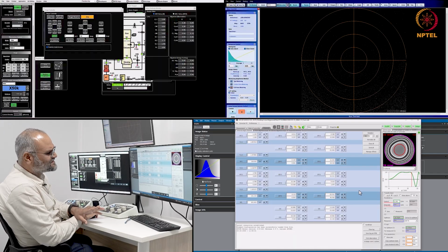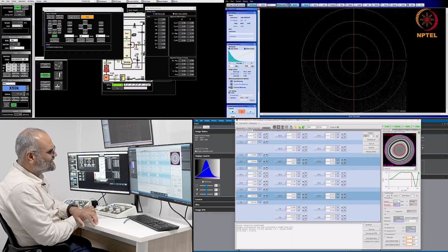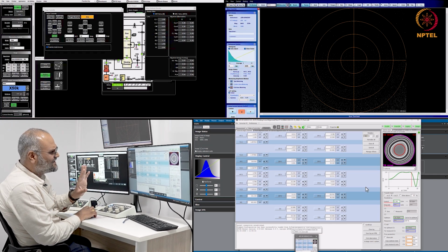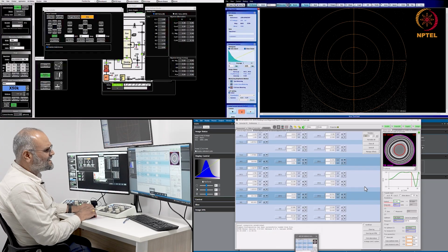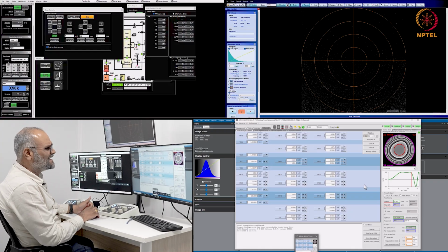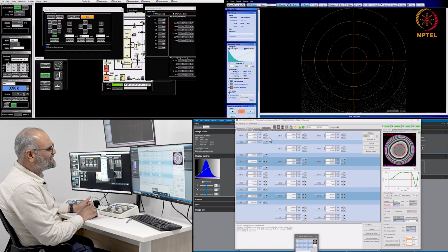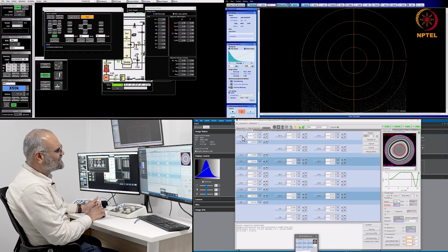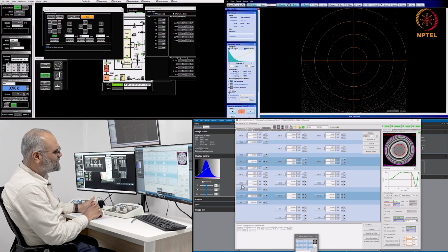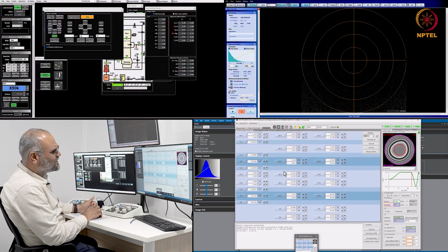To run the aberration correction, you go to this ATCore correction software and switch this on. Fortunately, everything is now automated through the program, and you can see that there are various lenses. Like shown a little while ago in the description of the position of the aberration corrector, you have several coils here. You have the hexapole lens, hexapole 1,1, hexapole 2,1, 2,2, and so on. And you have the transfer lens and the quadrupole.